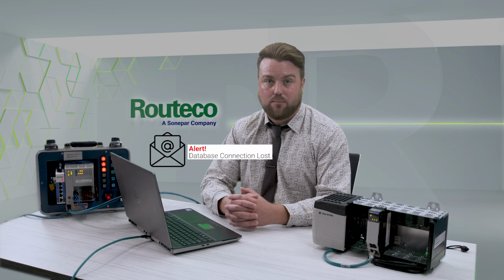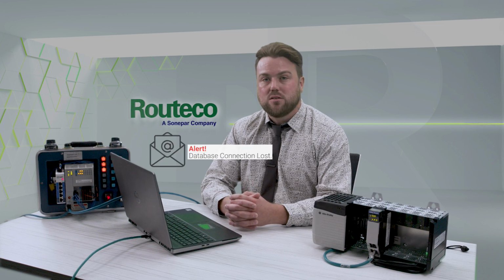A single module can be used to connect multiple PLCs to multiple databases. There are no limits on the number of tags transacted. Module status can be read via add-on profile, and an email can be sent out in the event of loss of database connectivity. Store and forward is built into the module. Connections can be read-only or read-write, so the module is suitable for data logging, recipe handling, and other applications where database connectivity is required.